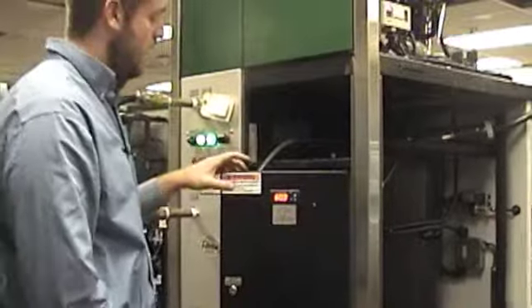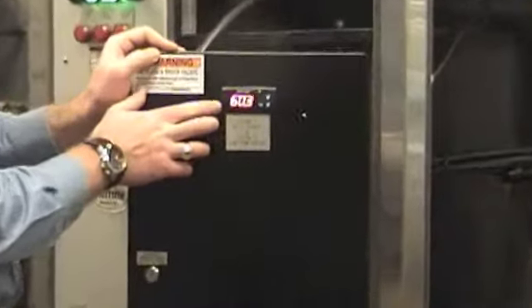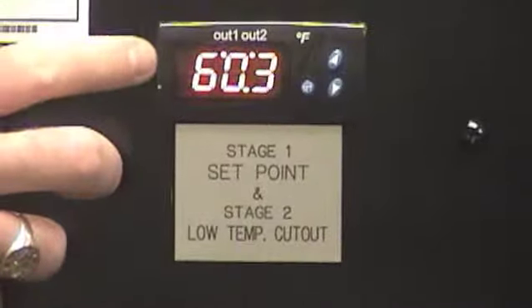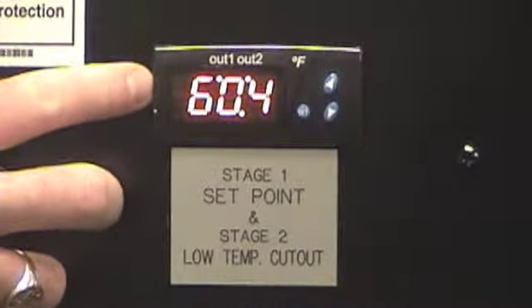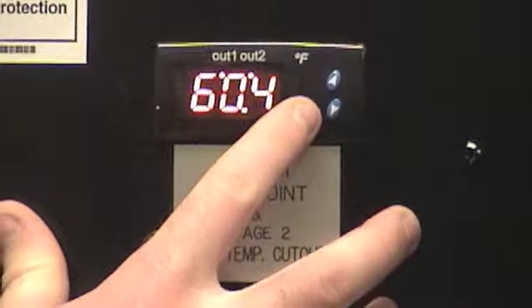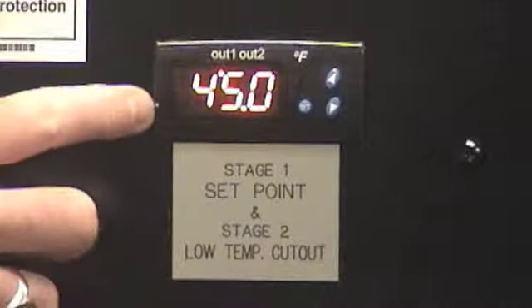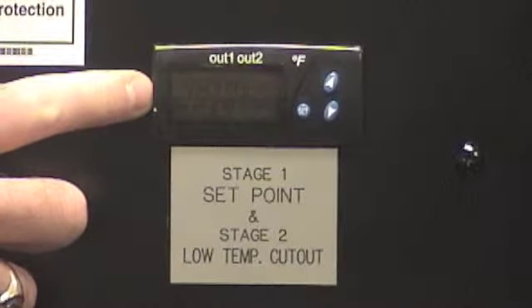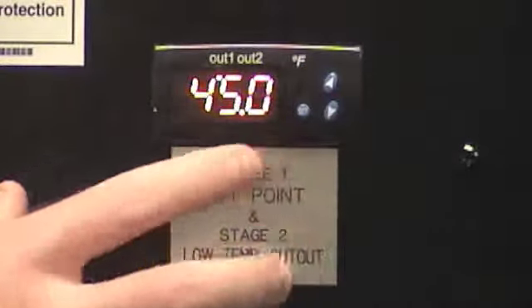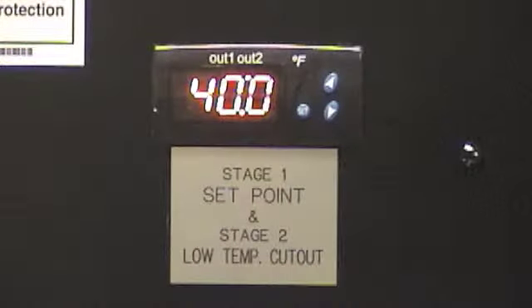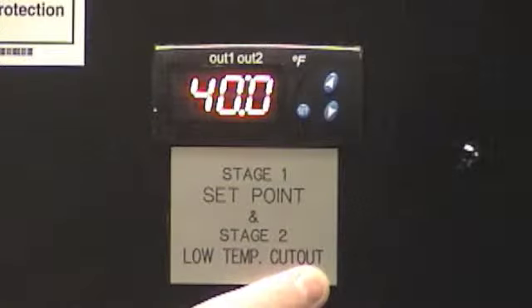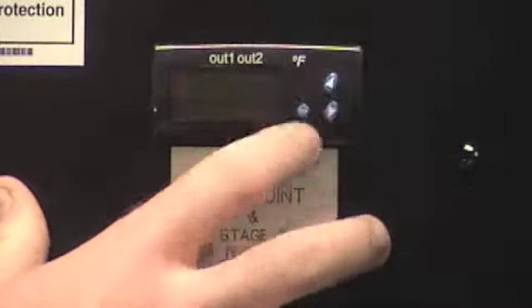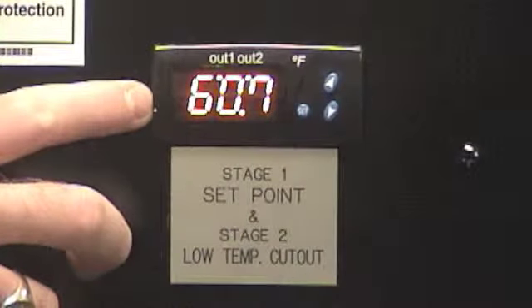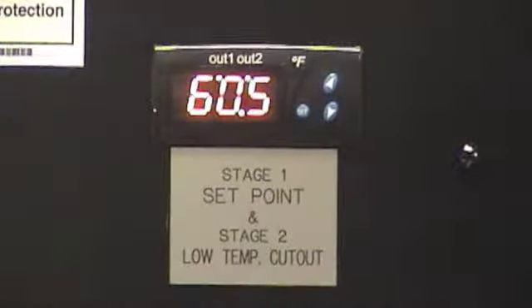Next, we're going to want to make sure that the set points are correct. We use the digital control on the outside of the electrical box. The first setting here shows the current water temperature. To change the set point, once you hit set, that's going to be your thermostat set point, which we have for 45 degrees. While it's blinking, you can adjust it up or down, however you want. But we'll keep it at 45. And then once you hit set again, that's going to give you your low temp cutout. Again, you can adjust that up or down. And once you hit set, it'll bring you back to the current water temperature. And this is how you're going to control your set points for the unit.